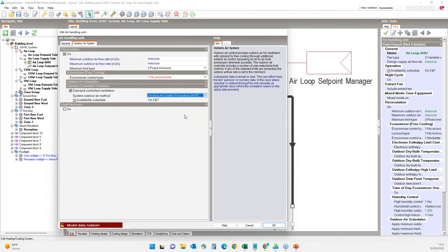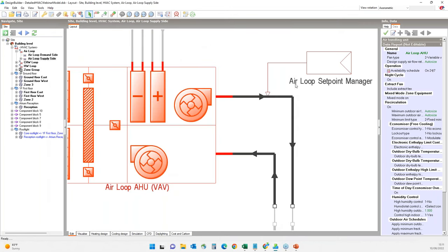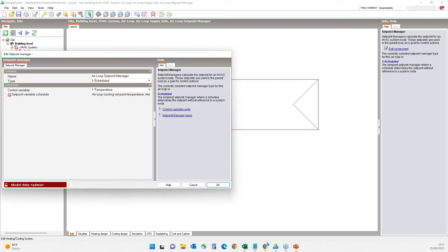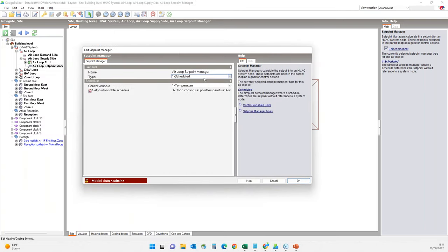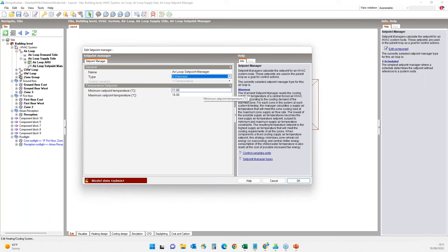The CO2 setpoint is defined in the activity tab, which I will show later. Because we have a demand control ventilation system, the minimum outdoor air flow rate needs to be zero. We can also enable heat recovery to make the system more efficient. Next, I need to change the setpoint manager to supply air properly. I will change the setpoint manager type from schedule to 'warmest,' with minimum and maximum setpoints of 14 and 18 degrees.